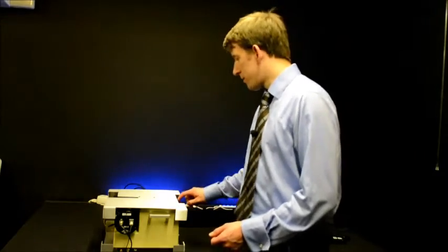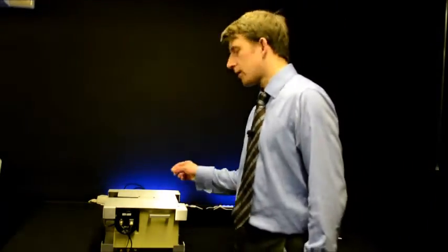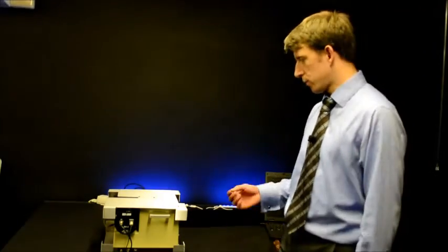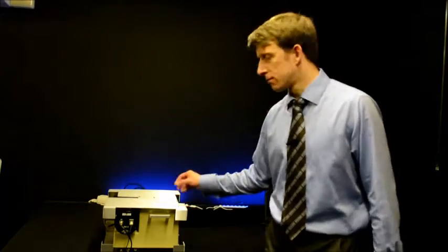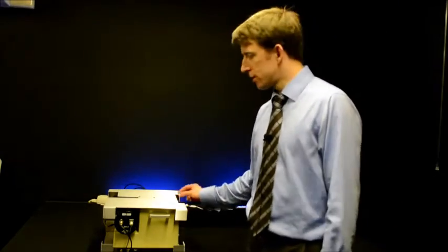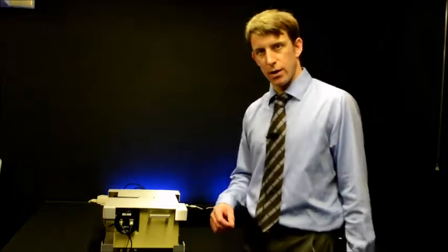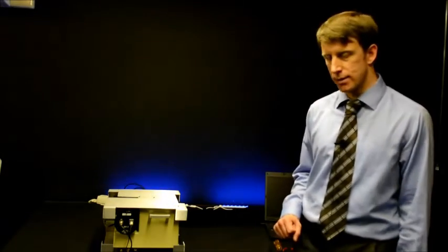With regards to the impact of the entrance slit on bandwidth, one simply needs to consider that the monochromator is an imaging optical device, and in fact what is present at the exit slit is an image of the entrance slit in all of the colours, or all of the wavelengths. Therefore, a large entrance slit will equally have an impact on bandwidth as a large exit slit. In practice, we tend to use a system with equal entrance and exit slits.